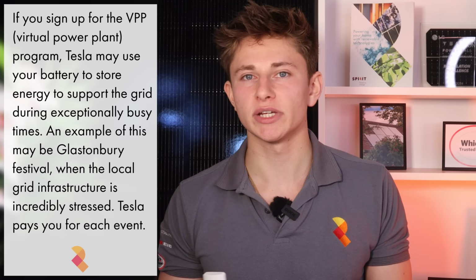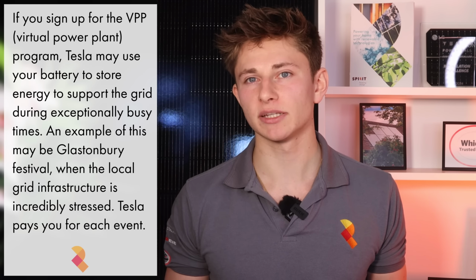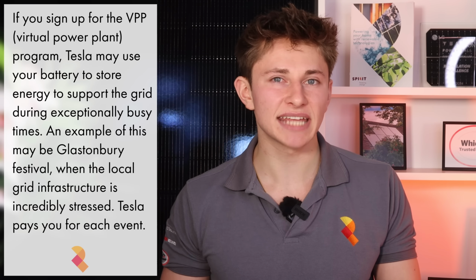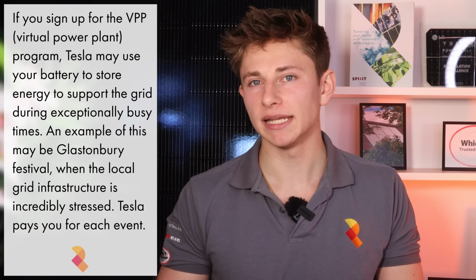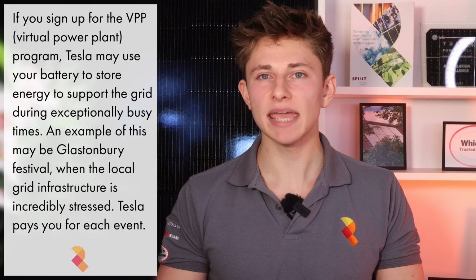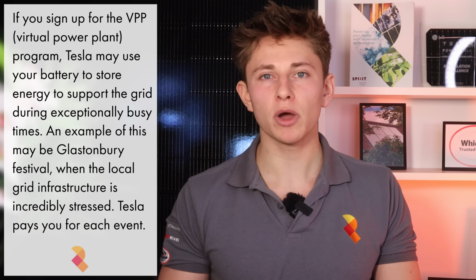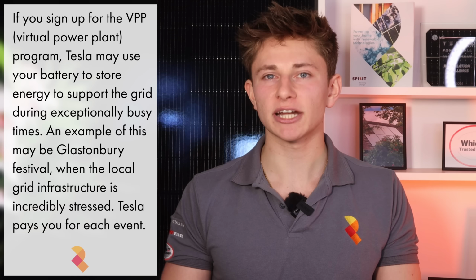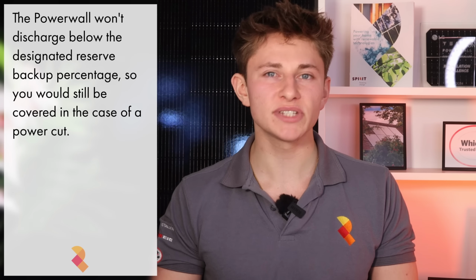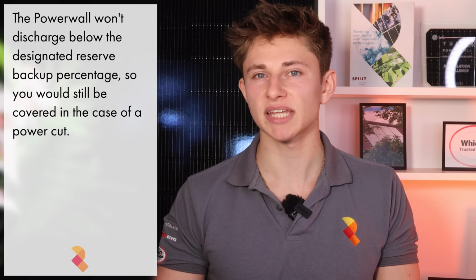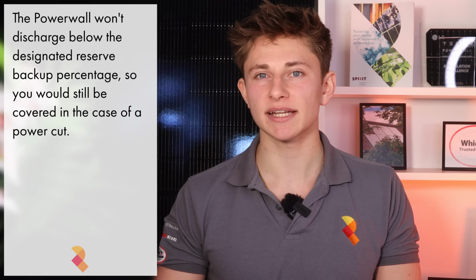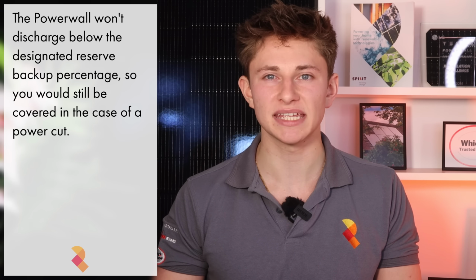One of the most exciting benefits is something called Virtual Power Plant, or VPP. VPP allows Powerwall 3 owners to join a network of home batteries that collectively support the grid during peak demand. For the most part, on a day-to-day basis, the Powerwall behaves completely normally. However, if VPP is enabled and there's a strain on the grid, the network of Powerwall batteries in your area will be dispatched to support the grid and help prevent outages. It's important to note that the Powerwall 3 won't discharge below the specified backup reserve percentage, so your house will still be protected if there's a power cut during a VPP session.